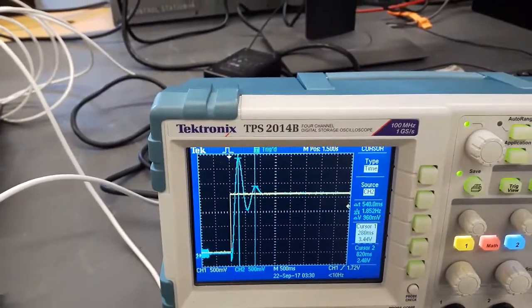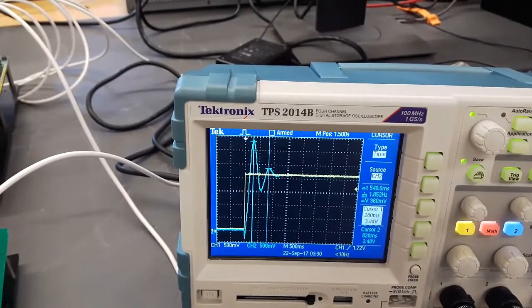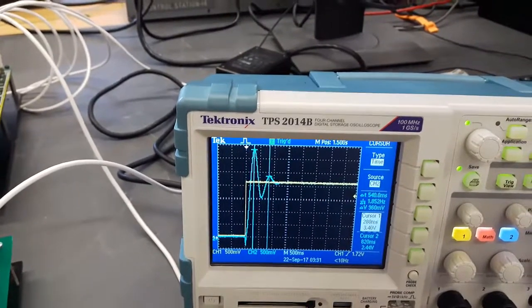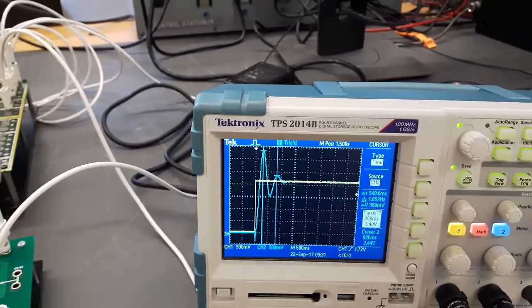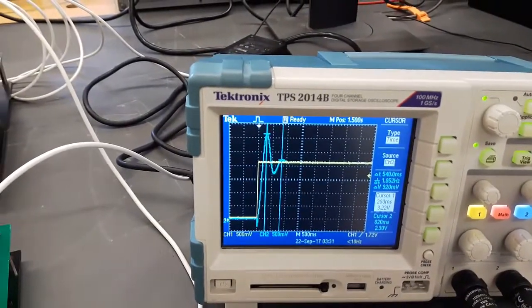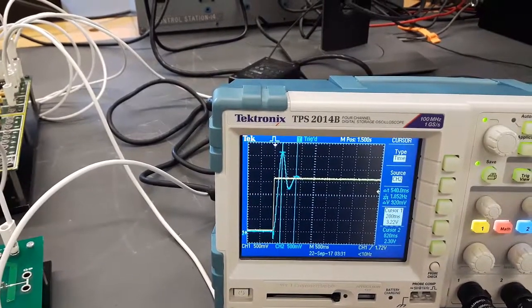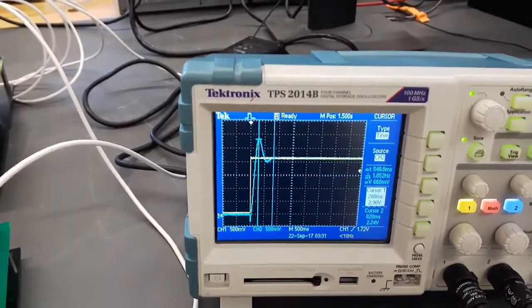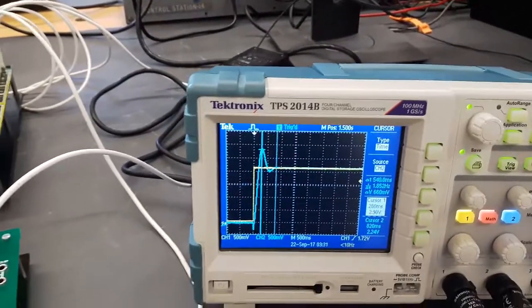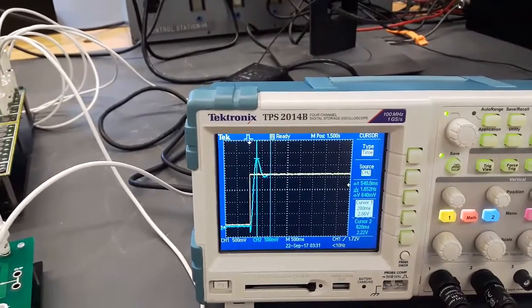So then I can increase my derivative. And I'm working at trying to reduce my overshoot. There we go. There we go, even farther down. Still stable, it looks like I've reduced it quite a bit.